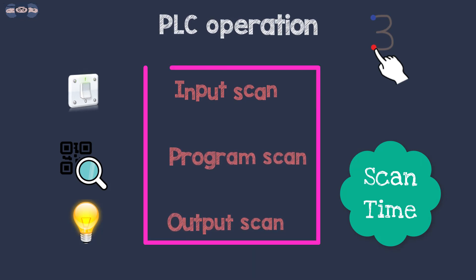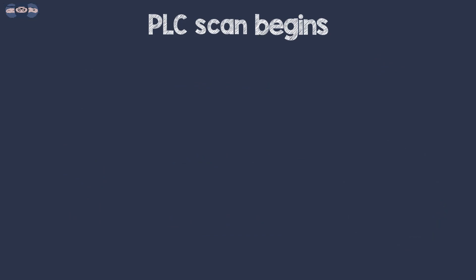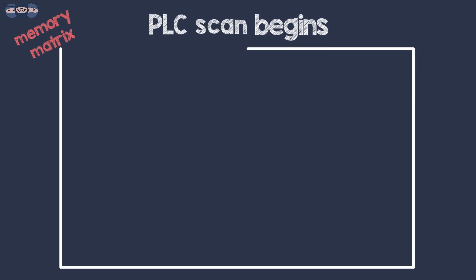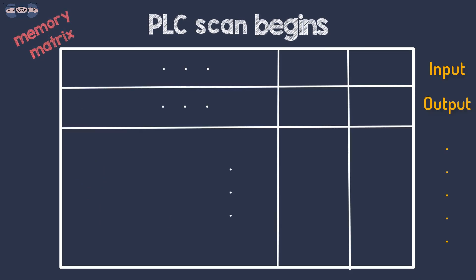The scan time is how long it takes the PLC to loop around the whole process back to the start. When the PLC scan begins, it maps the memory matrix for input and output. A discrete input can be designated by I and a discrete output by O, though this depends upon the PLC designer and manufacturer.